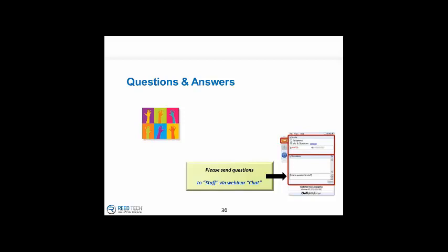Lynn also asks, please explain how you describe a package configuration in the description field. I wanted to think about that to make sure I understood what was going on there. So in a device description field, and there's a couple description fields, that's why it was a little confusing to me. The device description field is for the base product. So you can say this is an IV pump, and model 523 or whatever, serving this type of application.